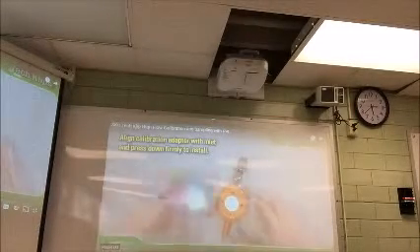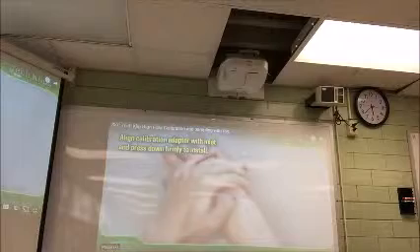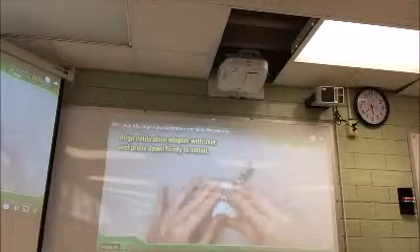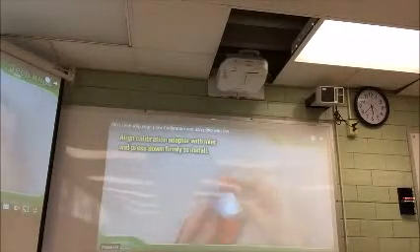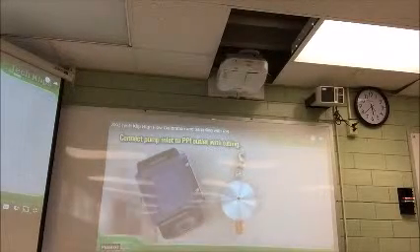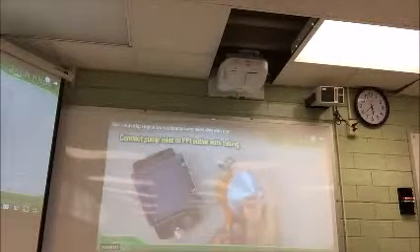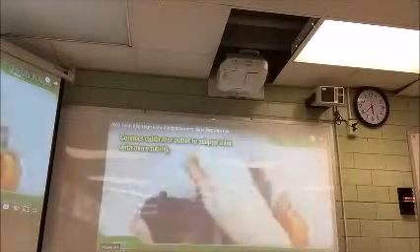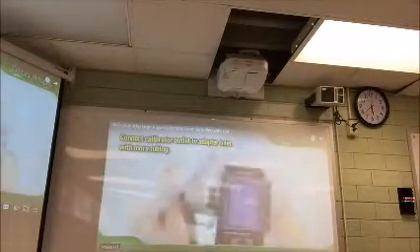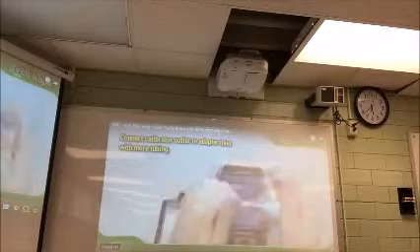Press down firmly and evenly for an effective seal. Remove the protective cap from the sampler exhaust. Install the calibration adapter on the sampler inlet. Be sure to establish a good seal. Connect the pump inlet to the sampler exhaust with tubing. Use a second length of tubing to connect the calibrator to the calibration adapter.